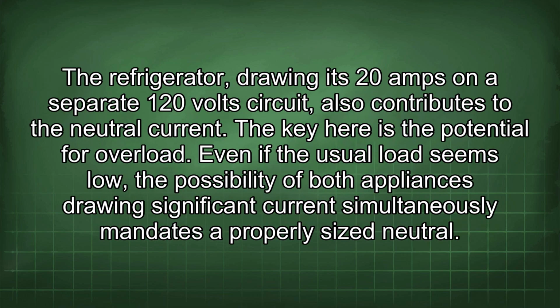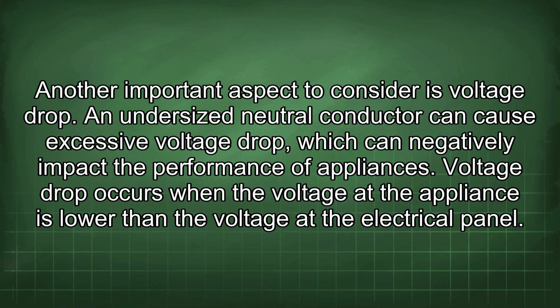The refrigerator, drawing its 20 amps on a separate 120-volt circuit, also contributes to the neutral current. The key here is the potential for overload. Even if the usual load seems low, the possibility of both appliances drawing significant current simultaneously mandates a properly sized neutral. Another important aspect to consider is voltage drop.